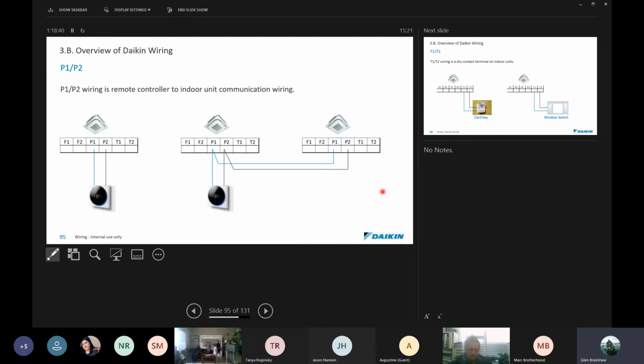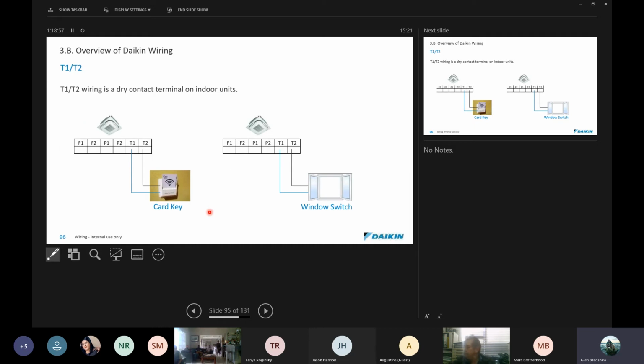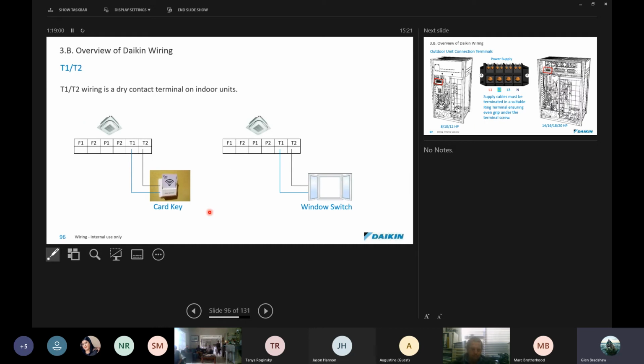On the indoor units, we've already discussed where the F1, F2 comes from. That comes from the outdoor unit, but all controllers are mounted on the P1, P2. It is possible to daisy chain multiple units onto one controller, up to 16 of them. Keep that in mind. The T1, T2 is used for card readers or window switches. It's a contact that can be used for switching units on and off or designating an alarm situation. So in hotels, they will put their card readers into here. When the person walks in and puts the key card in there, it will allow the unit to be switched on. When they take it out, the unit will be switched off.